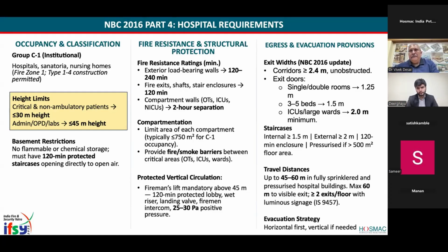So the idea is simple: when you have a positive pressure inside the lift well, if people are traveling during the fire escape, the smoke will not travel into the lift car. That's the reason. And also the staircases have to be positively pressurized, because it's an escape path. The smoke should not come from the premises into the staircase. That's the idea for keeping the positive pressure during the fire emergency.